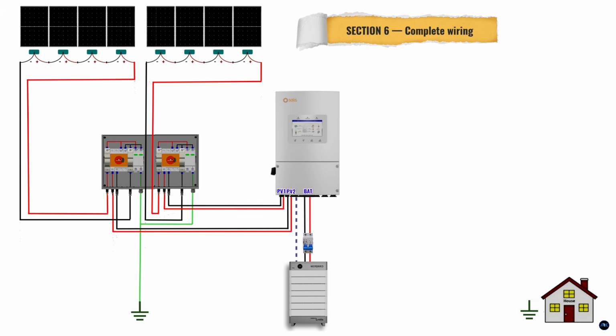From the positive bus, run 70 or 95mm squared flexible copper cable through the 200 amp DC battery breaker to the inverter's battery positive terminal. Keep this run under 1.5 meters. Use hydraulically crimped ring lugs. Never solder heavy battery cables. Connect BMS communication cable to the inverter if your batteries support it. The battery breaker stays open until commissioning.